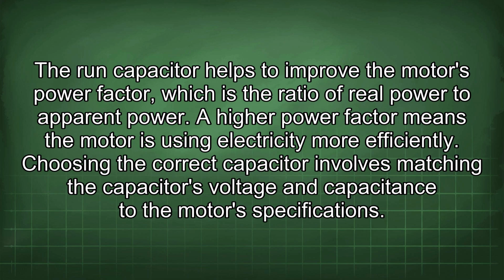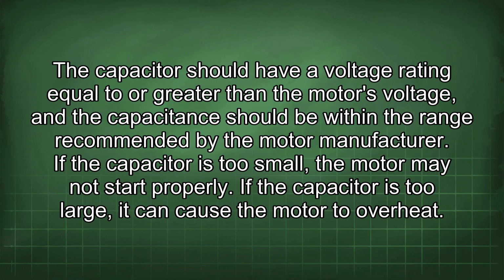Choosing the correct capacitor involves matching the capacitor's voltage and capacitance to the motor's specifications. The capacitor should have a voltage rating equal to or greater than the motor's voltage, and the capacitance should be within the range recommended by the motor manufacturer. If the capacitor is too small, the motor may not start properly. If the capacitor is too large, it can cause the motor to overheat.